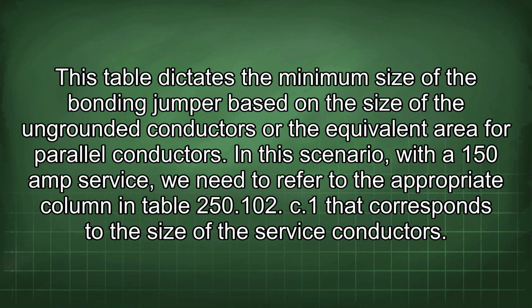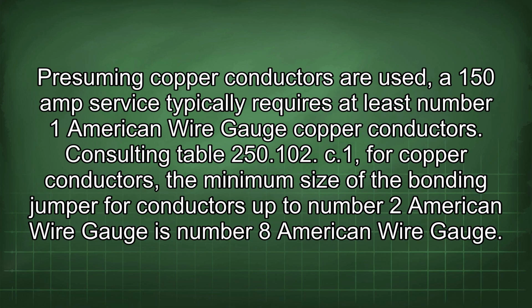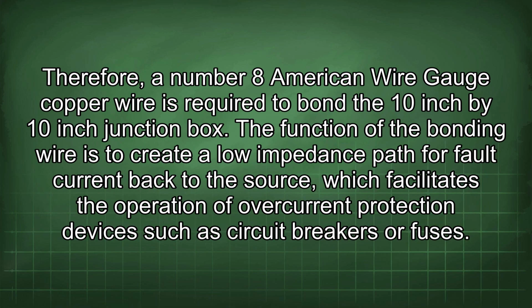In this scenario, with a 150 amp service, we need to refer to the appropriate column in Table 250.102(C)(1) that corresponds to the size of the service conductors. Presuming copper conductors are used, a 150 amp service typically requires at least number 1 American wire gauge copper conductors. Consulting Table 250.102(C)(1), for copper conductors, the minimum size of the bonding jumper for conductors up to number 2 American wire gauge is number 8 American wire gauge. Therefore, a number 8 American wire gauge copper wire is required to bond the 10-inch by 10-inch junction box.